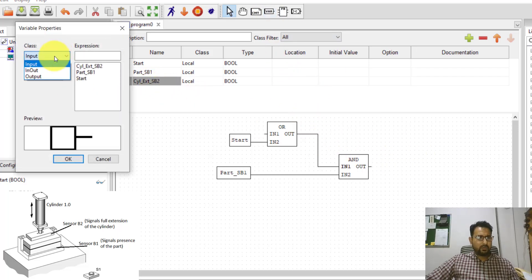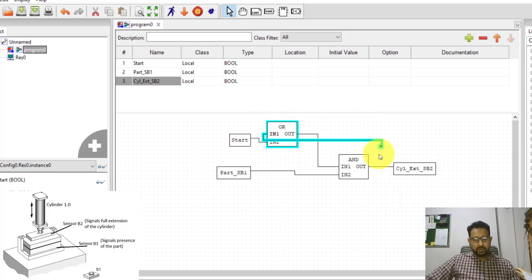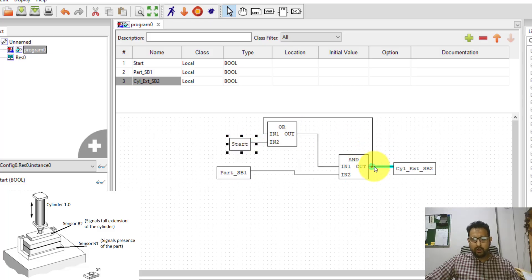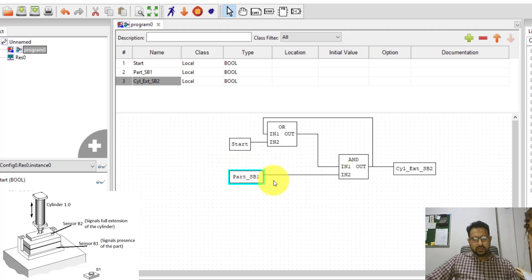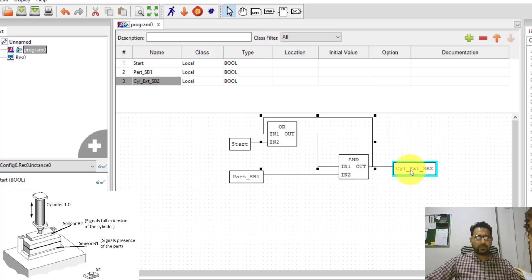When the start button is pressed and the cylinder is off, the OR gets 1 and 0, so its output is 1. With the part present, both AND inputs become 1 and the cylinder turns on. If the start button is released, the OR still gets a 1 from the cylinder feedback, so the output remains on. This is how you latch an output. Once the cylinder extension variable is on, meaning the cylinder has extended, I want a timer to run.